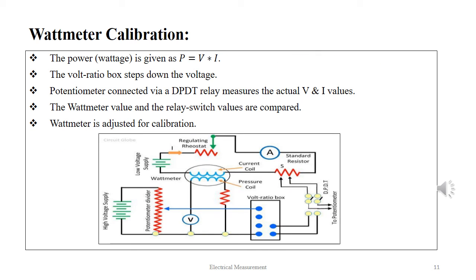As already mentioned, the setup of the wattmeter calibration is shown in the picture given. It principally has two coils, the voltage coil and the current coil. The power or the wattage is given by the formula P equals VI. The volt ratio box steps down the voltage. The potentiometer connected via DPDT relay measures the actual V and I values. The wattmeter value and the relay switch values are compared. The wattmeter is adjusted for calibration.